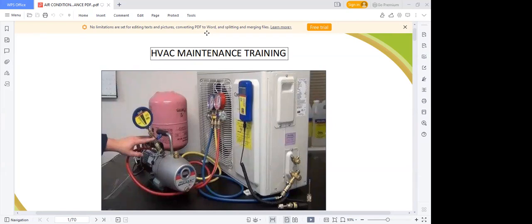Because I noticed that when some technicians want to do service, they don't like opening that up, maybe except once in a year or so. It's supposed to be something that will be done every quarter, or twice in a year, or once in a year. No, your fan should not be tampered with if your maintenance plan is followed as planned. The only time you can check it is when you see any physical defect, or you are hearing noise, or it's wobbling. Sometimes you just do a physical check and see that it's working fine. If you do your physical check and see that where the fan is located is not working as required, probably something is wrong with that fan. You need to replace it. Because if you leave it with time, it will start generating noise and affecting the performance of your unit. So it's not something you check almost every time. It could be once in a year, it could be annual, but what you need is to do a physical check.